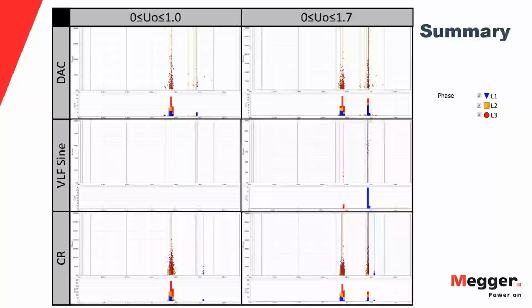What was done was that these splices were opened up and problems were found and addressed, so there was some repair work done. The PD activity that Jason showed you with the cosine rectangular in the cable insulation was in lead cable, like PILC cable, or let's say the European equivalent. It's called MIND, mass impregnated non-draining. It's very similar to PILC. Because it was not very high in magnitude and not very concentrated, it was pretty much left alone, so nobody opened the cable at that spot.